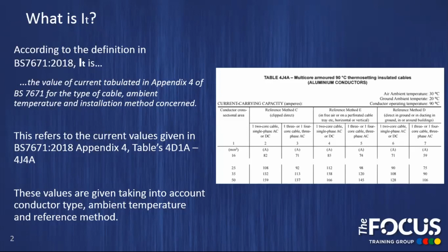So it's key to remember that the It values take into account conductor type, ambient temperatures and reference methods, but don't include the other rating factors.